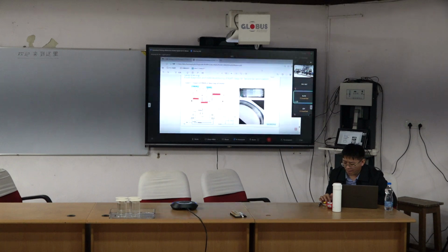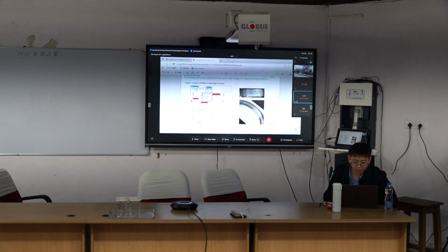And the third type of bearing current is the rotor shaft current, the yellow one. You can see the high frequency capacitive leakage current flows through the capacitor CWH between the winding and the housing, so the circular current must flow from the motor housing back to the inverter.